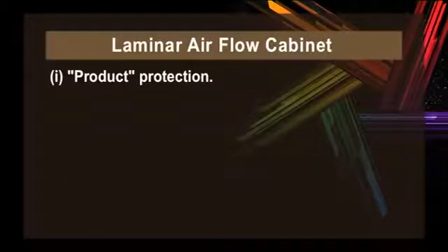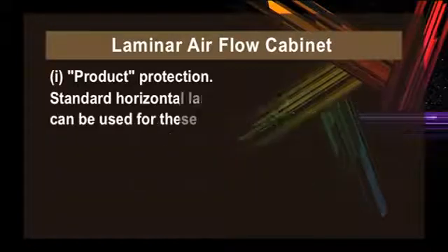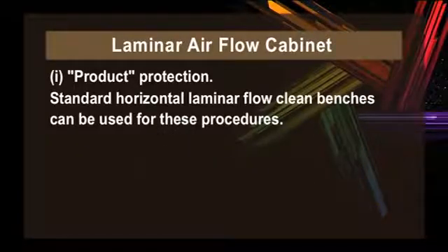Product protection. This area includes activities such as critical sterility tests and assays, aseptic filling and tissue culture preparation, and other procedures which require that the material be kept sterile, but where personal protection is not a problem. Standard horizontal laminar flow clean benches can be used for these procedures.